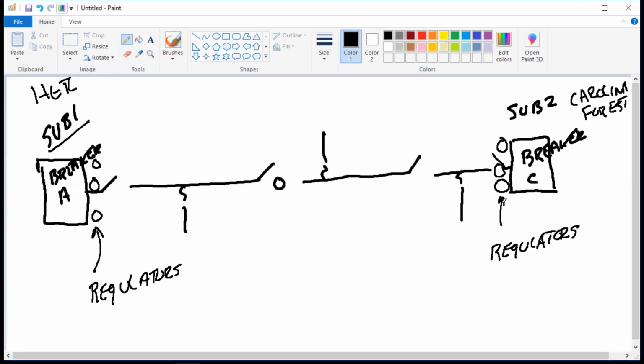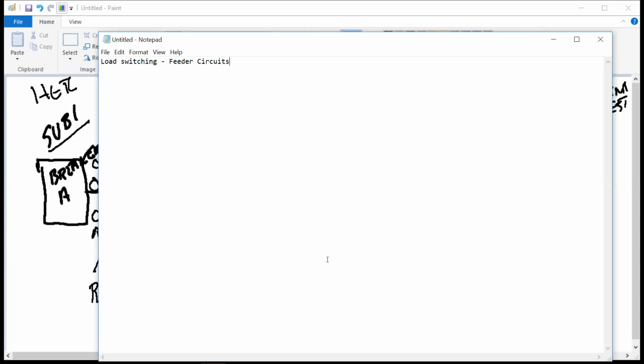Procedurally, and I'll type this out on Notepad for you also, the breakers and the regulators before we close a switch have to be what they call set up. You cannot put or move an open point in a system without first closing a switch. The objective here is not to have any customers without power while we do this. So on a feeder system, you must close an open point before making a new open point.